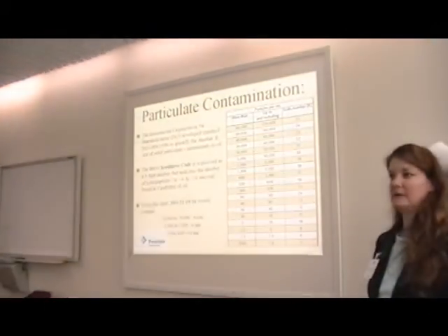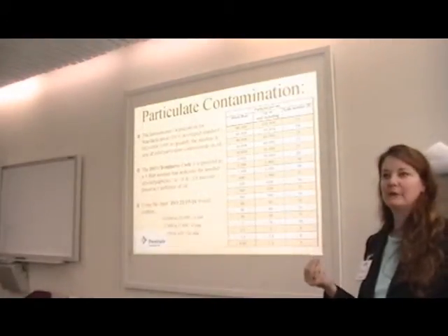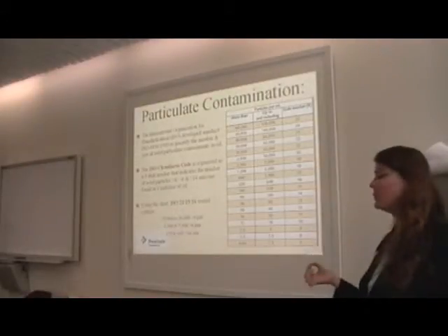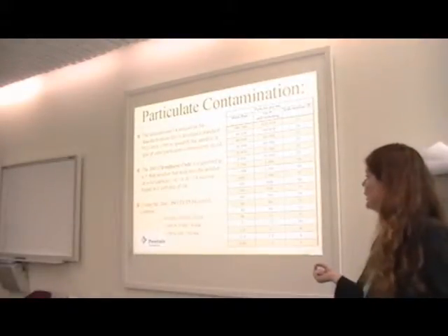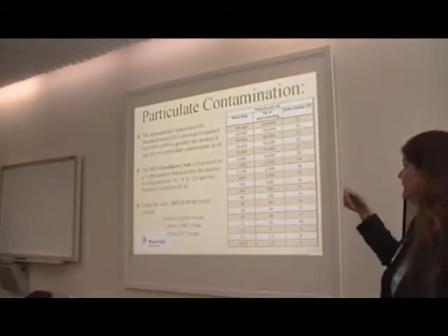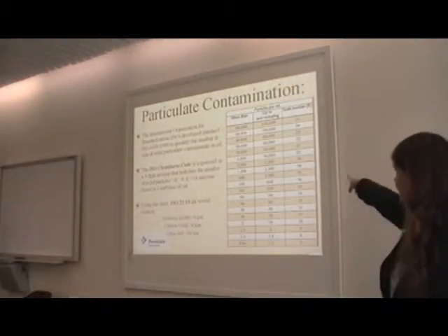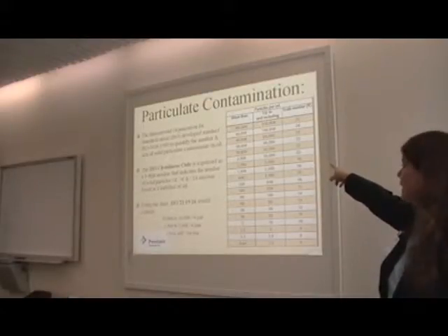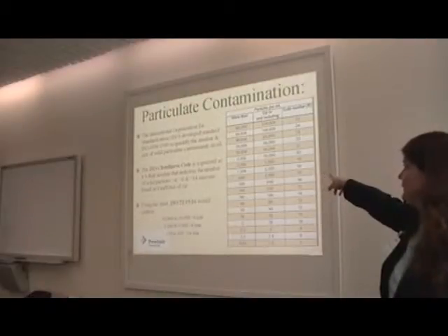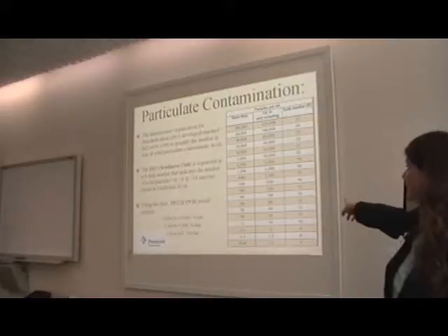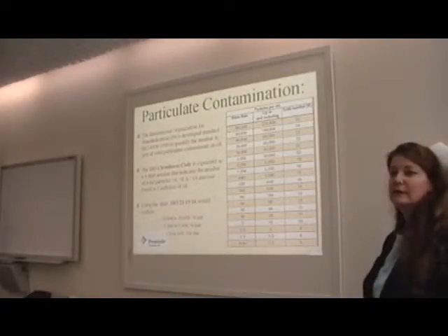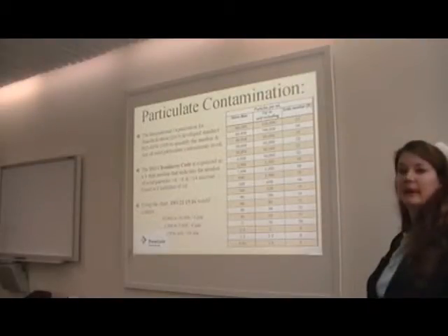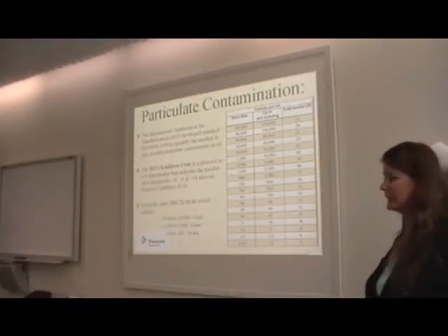So the cleanliness code is defining these 3 different micron values. Is everyone familiar with micron, I assume? Okay. It's the level of particulate that's greater than 4, greater than 6, and greater than 14 microns. If we were looking at this 21, 19, 16 example, over here on the far right column of our scale, we've got 21, which means there are 10 to 20,000 greater than 4 microns. And the 19, we've got 2,500 to 5,000 greater than 6. And then down here at the 16 level, we've got 320 to 640 greater than 14. So that's a pretty clean oil. And of course, they can go finer, as you guys are with your turbine oils. Exactly.